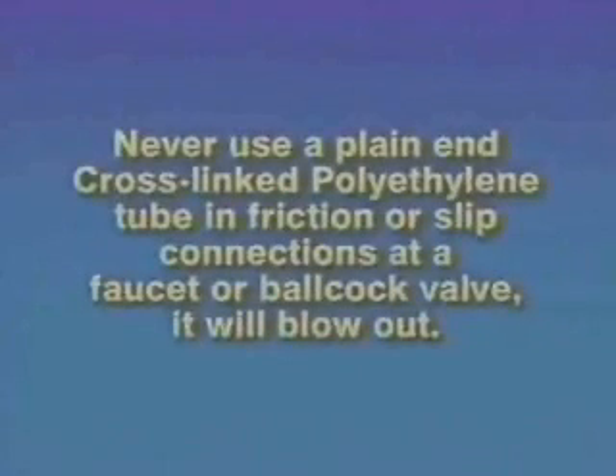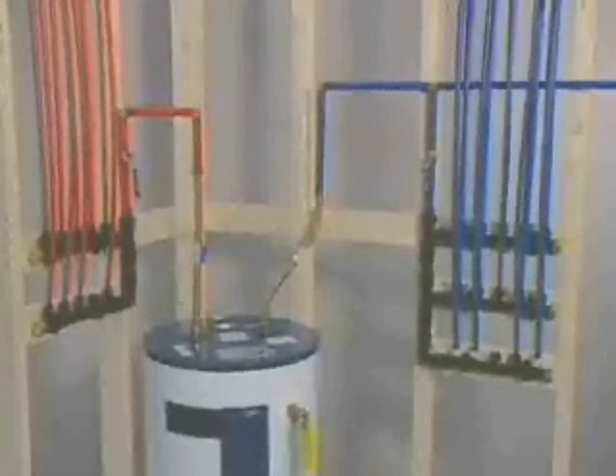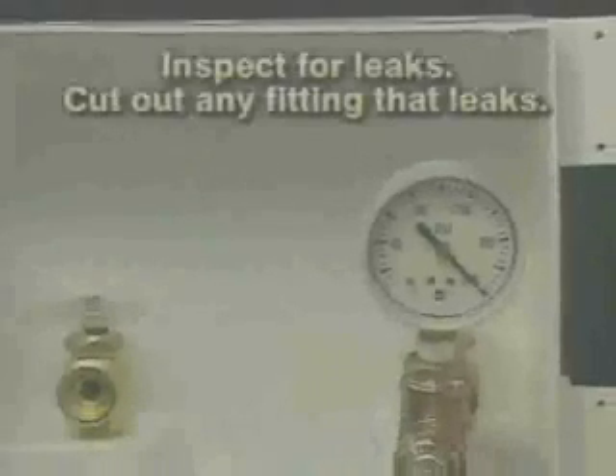For main shut-off valves, we have ball valves with insert ends for crimp installation in a cross-linked polyethylene line. When you have the ZurnPEX system locked in, we recommend a pressure test. First, fill the system with water. Pressurize it to 200 psi. Then hold that pressure for two hours. After this process, inspect the installation for leaks.